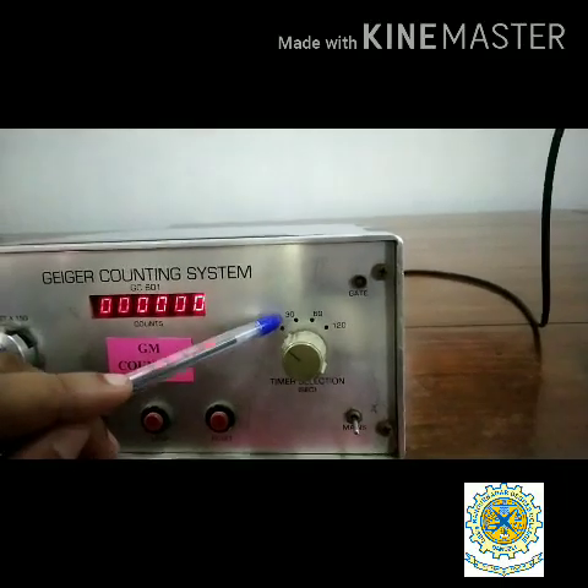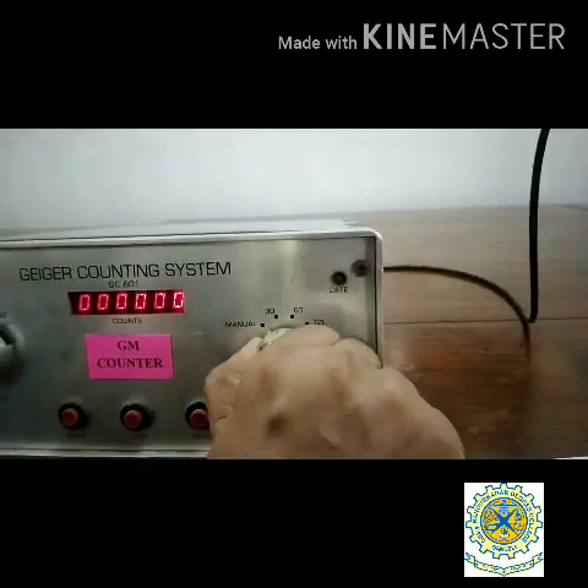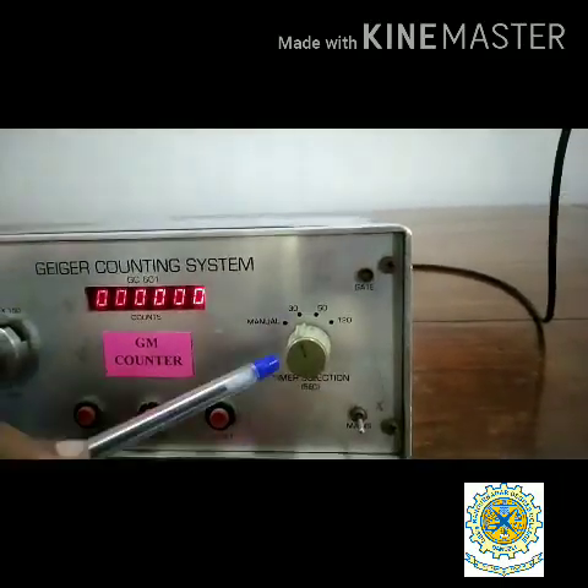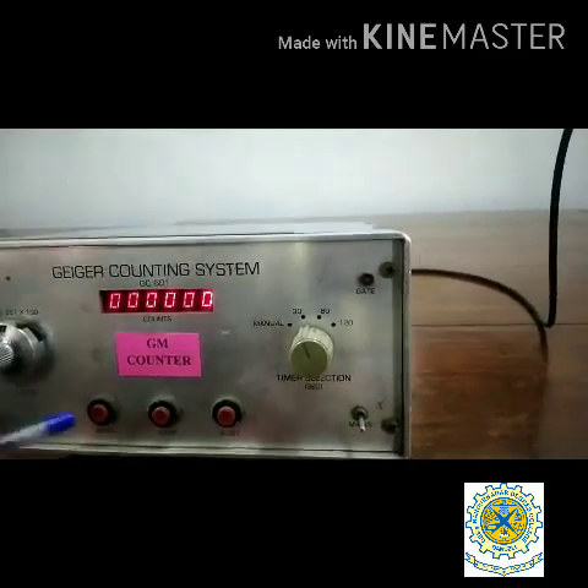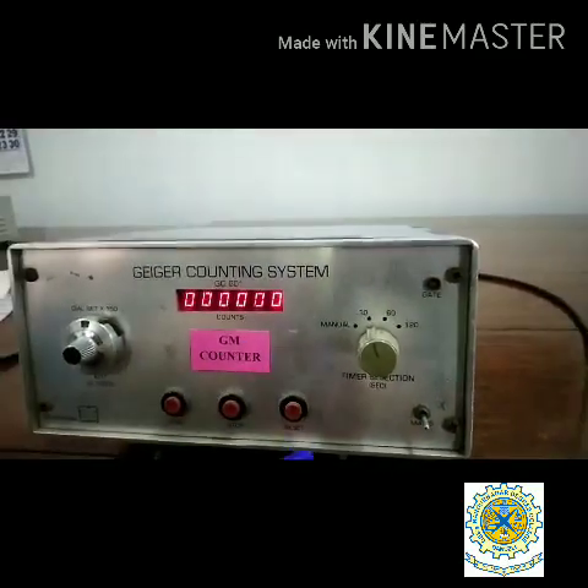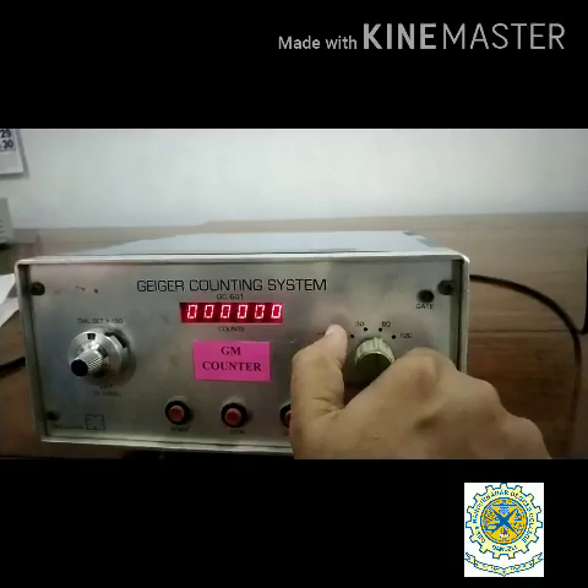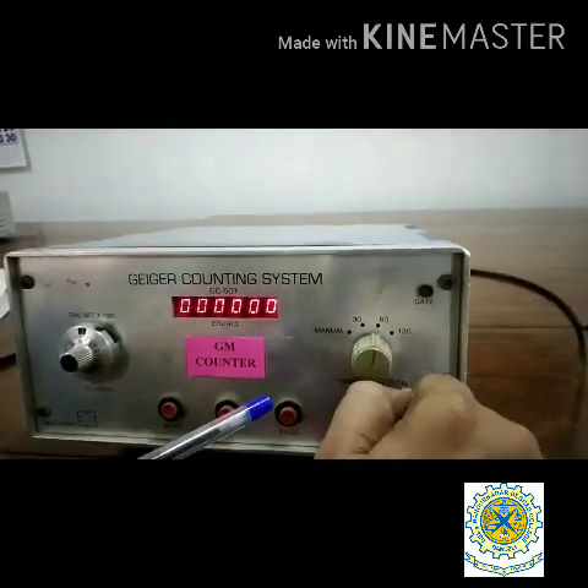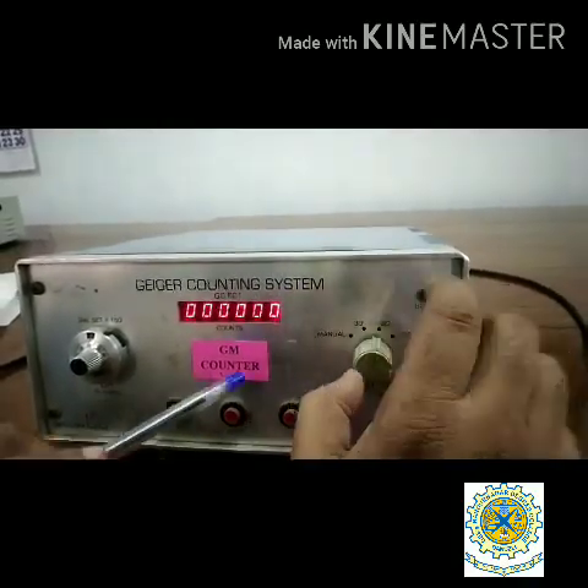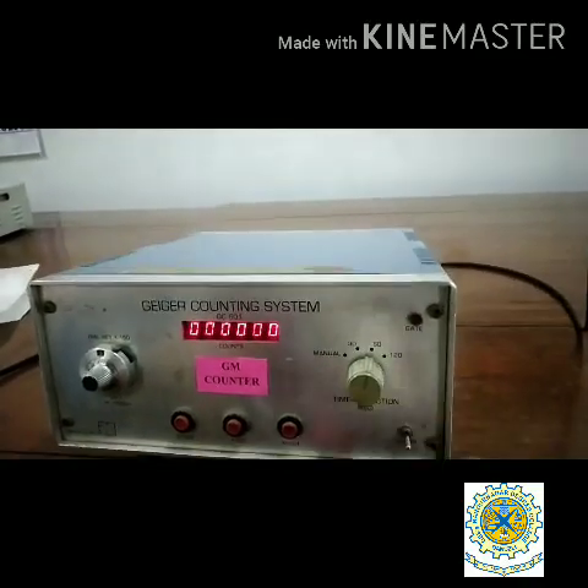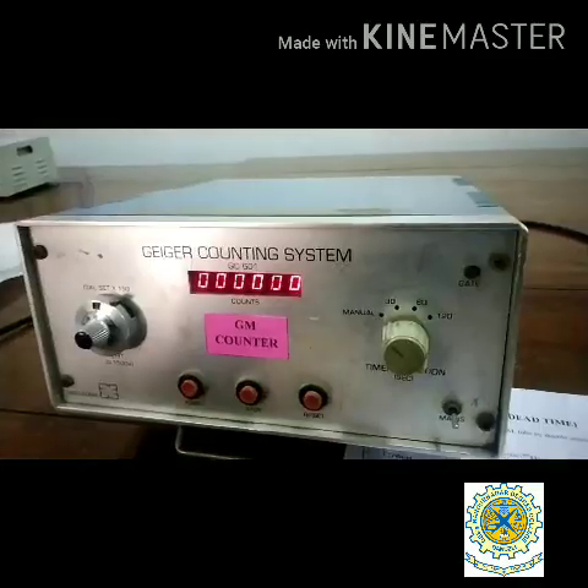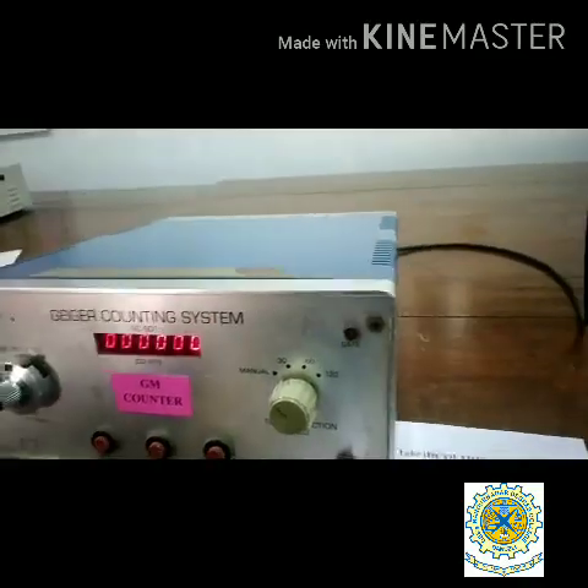If I put this button on 30, that means the counts are done only for 30 seconds. If I click on 60, then the count rate is counted till 60 seconds. Similarly for 120 seconds. Now we explain regarding the GM tube.